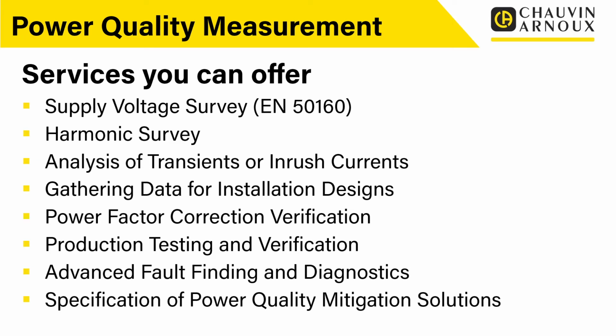Next one, power factor correction verification. So if we've got power factor correction within an electrical installation, is it working? Was it installed 20 years ago based on the equipment that was in the factory then, and nobody's actually tested it since? Nobody's actually sure whether it still works. Nobody's aware whether it's even doing its job. Obviously, using these products, we can measure the power factor. We can look at it with the power factor correction equipment connected, and look at it with it disconnected. You can see the difference.